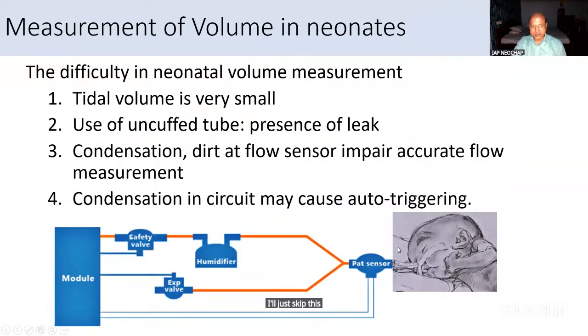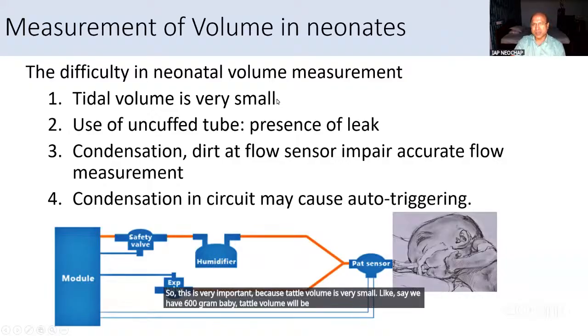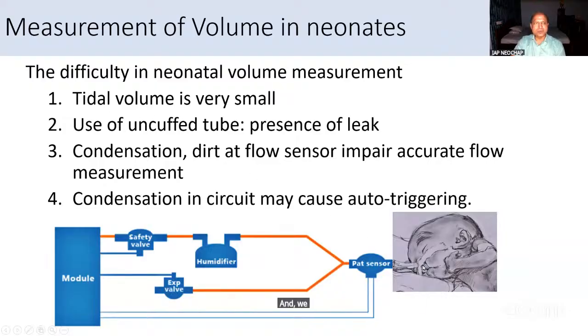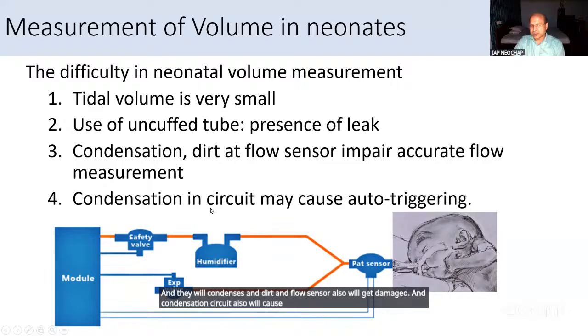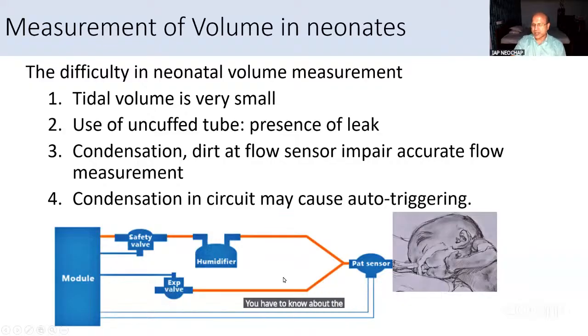So how do we measure this flow? This is very important because tidal volume is very small. Like say if we have a 600 gram baby, tidal volume will be almost 3.5 to 4 ml. And we use cuffed tubes, uncuffed tubes also, so there will be leak also. And there will be condensation, dirt, and the flow sensor also will get damaged. And condensation in the circuit will also cause auto triggering. So many things are there. So you have to know about the flow sensor, how it works, and which flow sensor should be used.